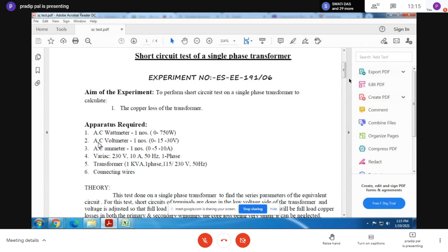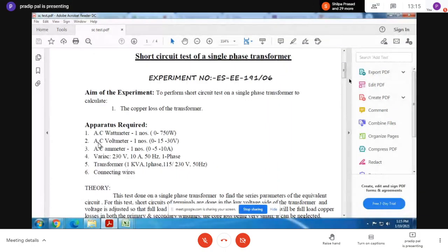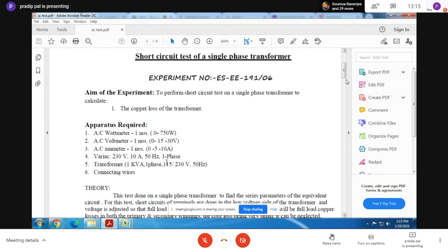This kind of loss generally appears in the secondary side from where we take the output of the transformer. In this experiment, we are going to short the output terminals of the transformer, then provide the primary side with a 230 volt 50 hertz AC supply, and then measure the input voltage, the primary current at full load condition, and the input energy. From those three readings we will calculate some things. Let's see the calculation part.